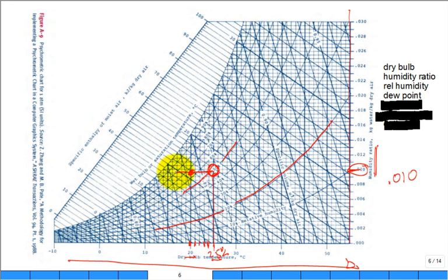If I continue to cool it, I'll finally get to a point where it is saturated air. What is the temperature now? Around 12–13°C. So that's the dew point temperature for those conditions. It doesn't mean I have to physically cool it — it just means if I do cool it, it will condense at 12°C.